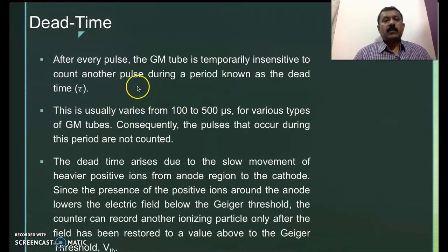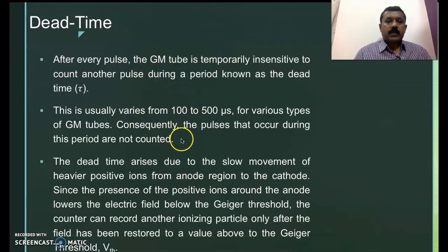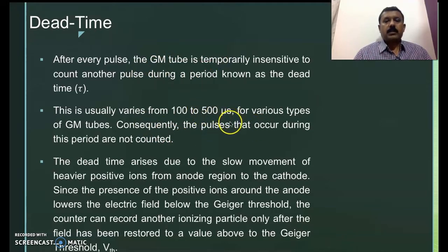The typical value of this dead time for various types of GM tubes ranges from 100 microseconds to 500 microseconds. Consequently, the pulses that occur during this time are not counted.